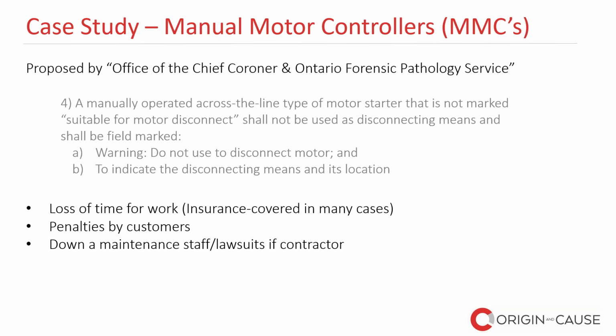newest version of the Ontario Electrical Safety Code is a new code rule that indicates a manually operated across-the-line type of motor starter that is not marked suitable for motor disconnect shall not be used as a disconnecting means, and shall be field marked "Warning, do not use to disconnect motor." So you can use it as an on-off switch, but you can't use it when you're maintaining equipment. And 2, it actually has to indicate now what the disconnecting means is and where the location of the proper disconnecting means is, to be able to safely do the work.